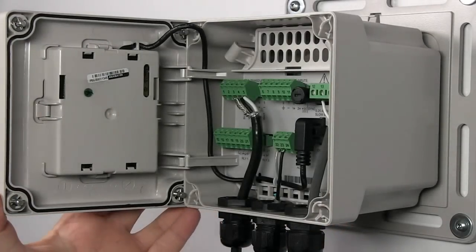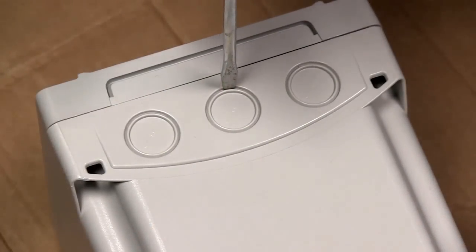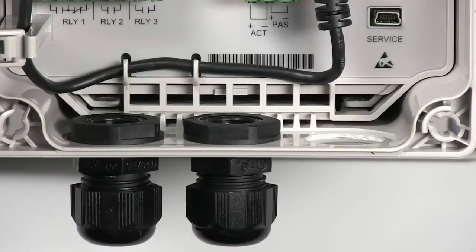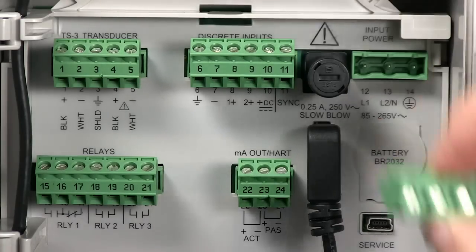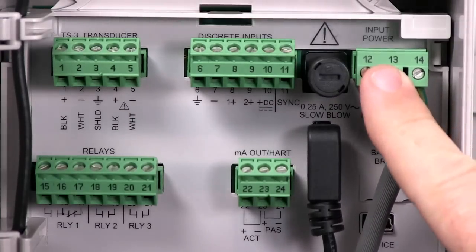The SITRANS LUT400 makes wiring convenient and easy. The wiring knockouts on the bottom of the enclosure are easily opened with a standard screwdriver. Insert half-inch NPT conduit fittings or M20 cable glands and run your wires. Pull any terminal from the socket, clamp the wires in place, and replace the terminal in the socket.